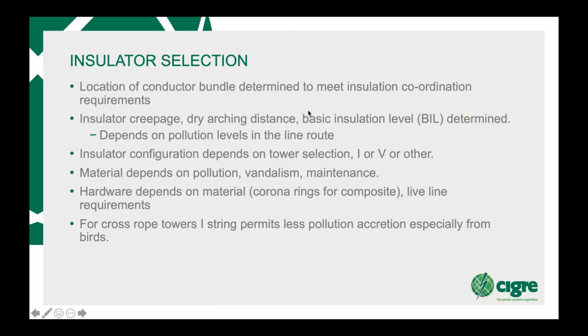Looking at the next line, you look at the insulator selection. So the location of the conductor bundle is determined to meet the insulation coordination requirements; you need to determine that. In other words, where is the point in the tower window that the conductor bundle needs to be positioned. You need to understand insulator creepage, dry arcing distance, and basic insulation level, and this depends on the pollution levels in the particular line route. There are books around on how to do that and determine what pollution levels relate to which creepage, how you actually design that, and what specifications you use to ensure that your insulator is in fact the correct one.